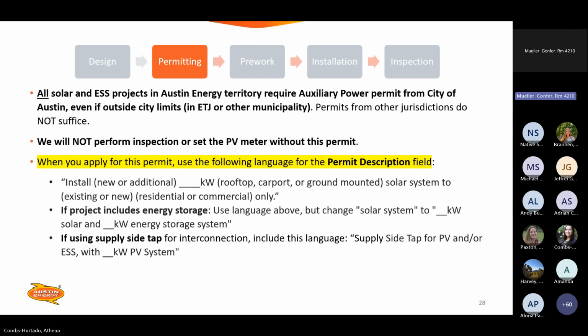Like I said, all solar and ESS projects in our territory require an auxiliary power permit from the city of Austin, so you'll see that in the drop-down menu on the ABC portal. Even if you're outside of the city limits, if there's an Austin Energy meter, you have to have an auxiliary power permit because we will be out there to inspect. Permits from other jurisdictions do not suffice. You may have to pull one of those, but you'll also need an auxiliary power permit. We will not perform an inspection or set the PV meter without this permit.